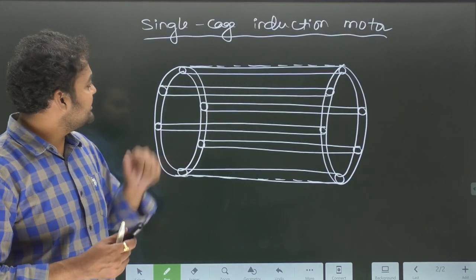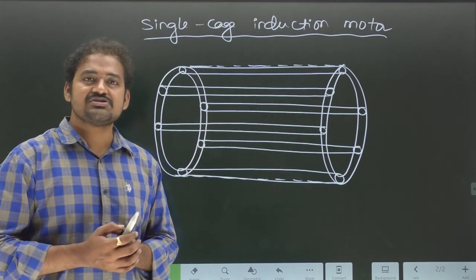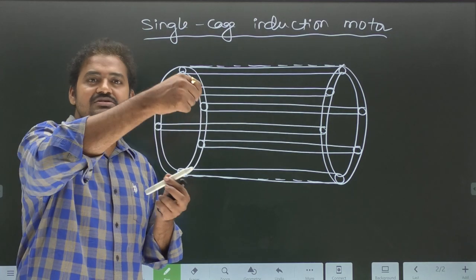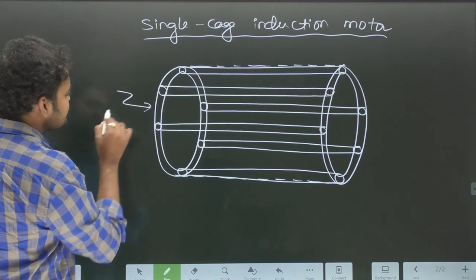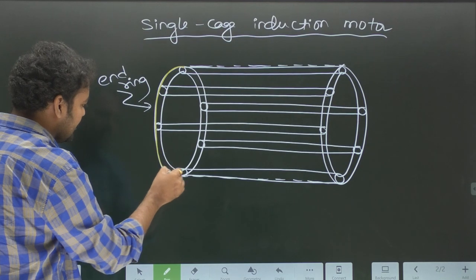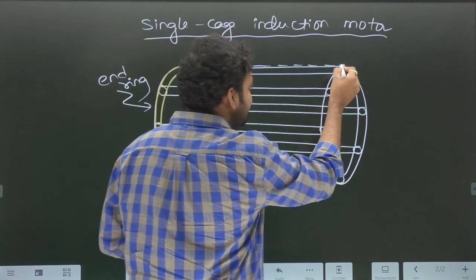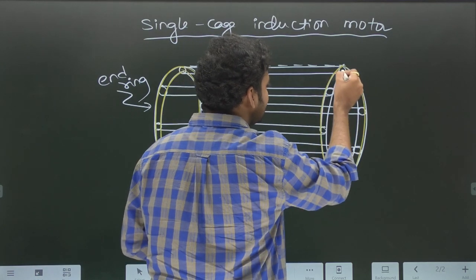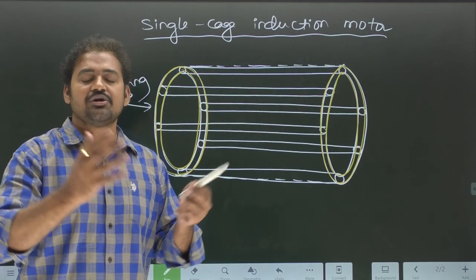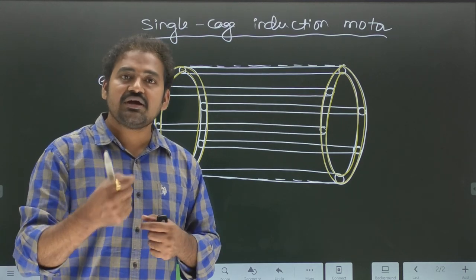In case of a squirrel cage or single cage induction motor, the rotor magnetic circuit consists of a number of copper bars located on the outer surface of the rotor using slots. All these copper bars are short-circuited on both sides using an end ring — a conductor made of either copper or aluminum. Similarly, on the other side there is one more end ring. As it is short-circuited on both sides, we cannot add additional resistance into the rotor, and that is why higher starting torque is not possible.